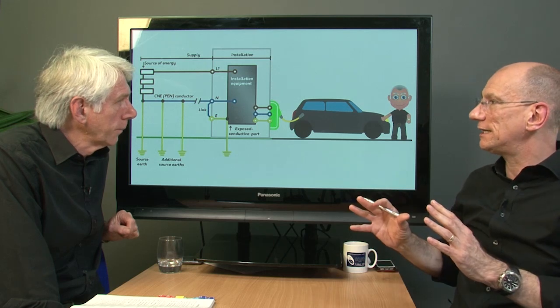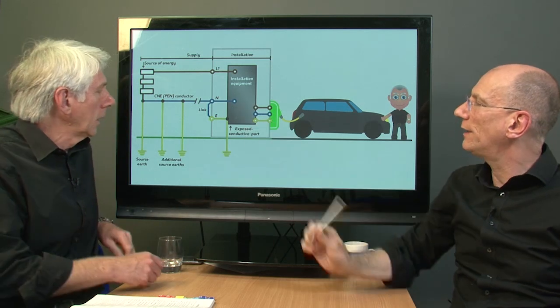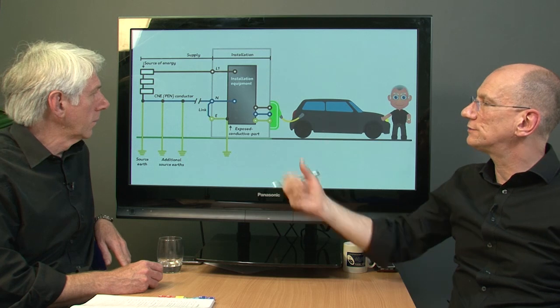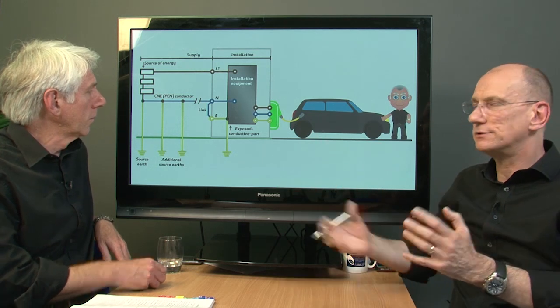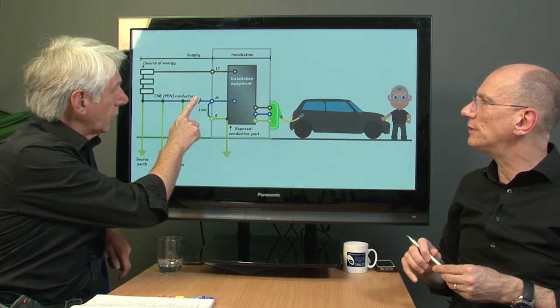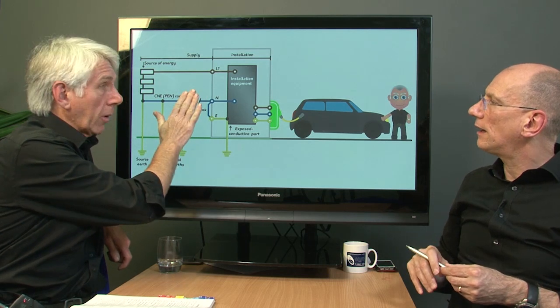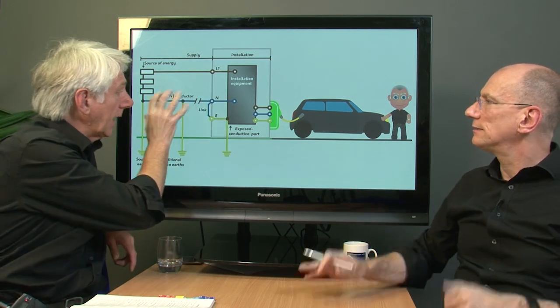This is not TT. This is basically stating that if you end up with a broken neutral, there is an alternative path - and the more we have of those, we'll possibly see this coming in an amendment. We should cover that up, because at this point, that isn't broken, is it? That isn't broken, so this is just standing by in case that happens.